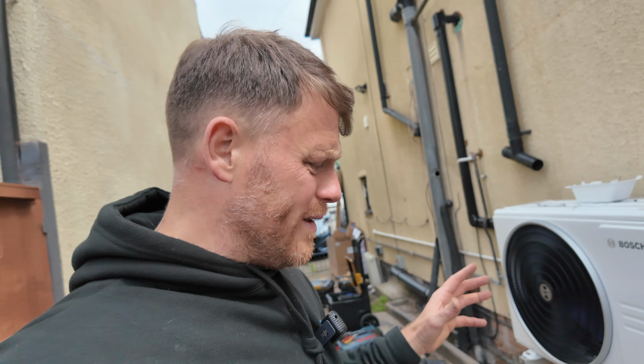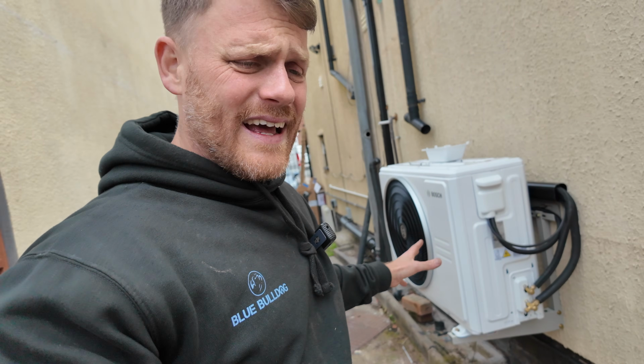This is a 5.3 kilowatt unit. You've probably already noticed the outdoor unit's in, piped up, wired up, all the way to the indoor. Since I've done videos before showing the outside connections and electrics, today I want to focus on the indoor connections. We've got a condensate pump to put in, and I'm going to show you the commissioning and testing procedure, so you can see how we make sure these units are running safely and efficiently. So for now we've got the outdoor unit in, pipework done, we're just moving on to the indoor unit. Let's go take a look.